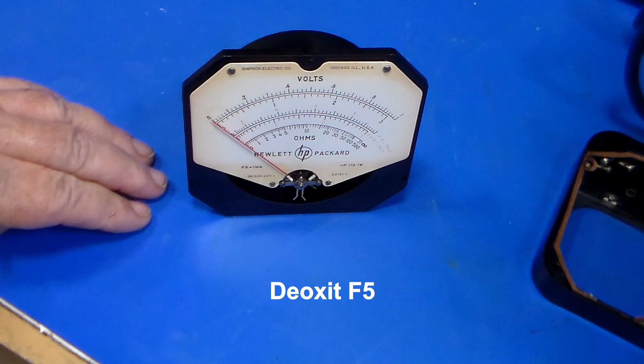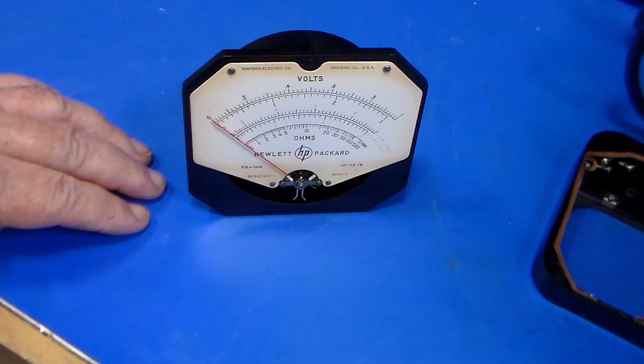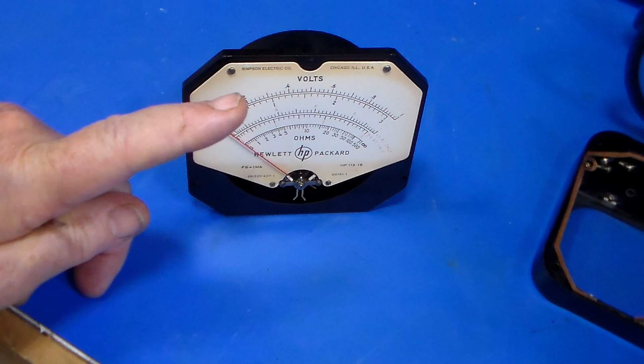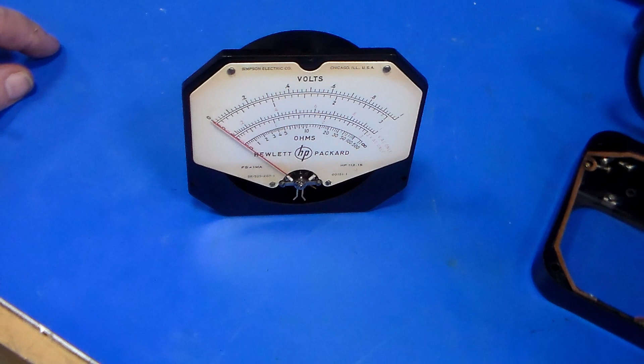So quite possibly it was more likely the bearings in the meter had accumulated some dust and dirt over the years, and the spraying of Deoxit F5, I think, actually moved the position of that dirt and grime closer to the 0 point and got rid of it in the areas where the meter was actually sticking at the 20 to 40% range. So that's now fixed, and I was able then to actually do a proper DC calibration, and I'll talk more about that in a moment.